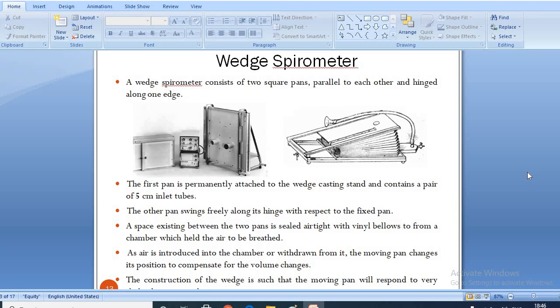As air is introduced into the chamber or withdrawn from it, the moving pan changes its position to compensate for the volume changes. The construction of the wedge is such that the moving pan will respond to very slight changes in volume. The transducers are attached to the fixed frame and are coupled to the edge of the moving pan. One transducer produces a DC signal proportional to displacement or volume while the other has a DC output proportional to velocity or flow. The transducer outputs are connected to an electronic circuit which contains the power supply, an amplifier and the built-in calibration networks.